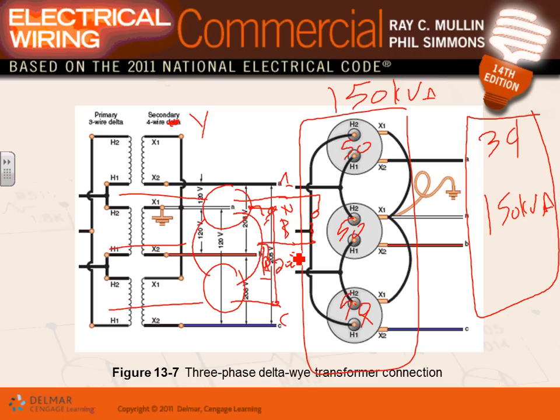Yeah. Adam? So that picture you drew right there, the 208, that line from C to neutral. Yep. So it hits C and B. No, it's just a neutral. So here's my neutral. It actually should be phase B if you connect them right. From this phase to the neutral, it's 208.